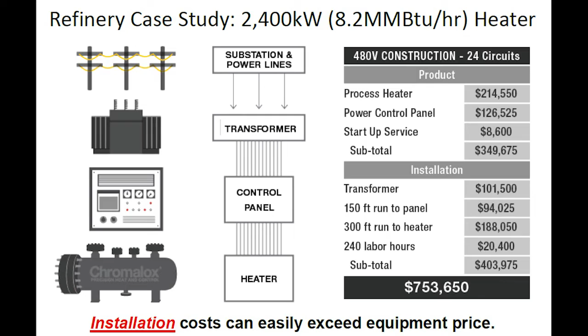And this is where medium voltage really kicks in. So the cost drivers of installation that are high when it comes to low voltage systems would be things like the transformer. Most systems in a plant are going to be sort of at capacity. When you introduce a new heating process that may require multiple megawatts, most likely they're not going to have the power available. Bring in the substation or add capacity for that load. And when they do that, they're going to need transformers again to step it down. So that's a significant cost savings to apply that heater in that application.